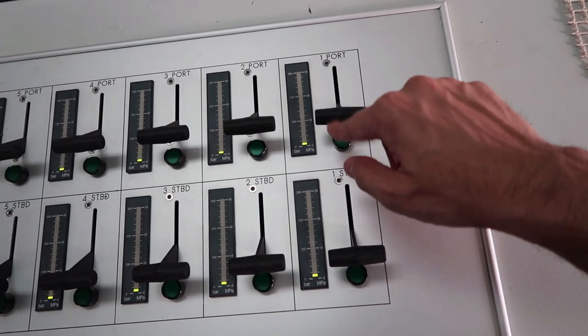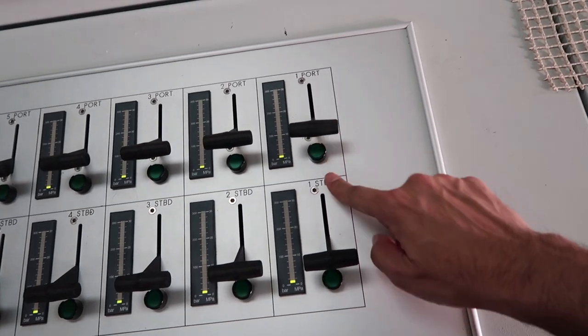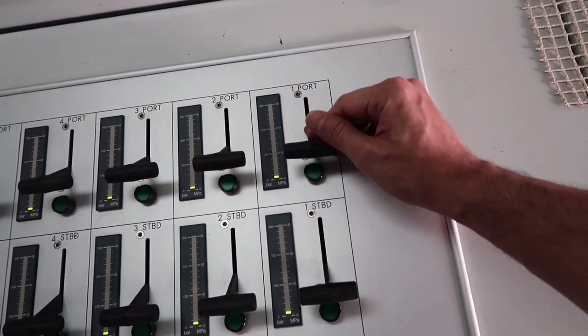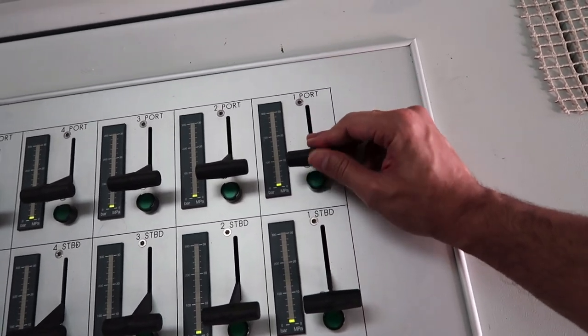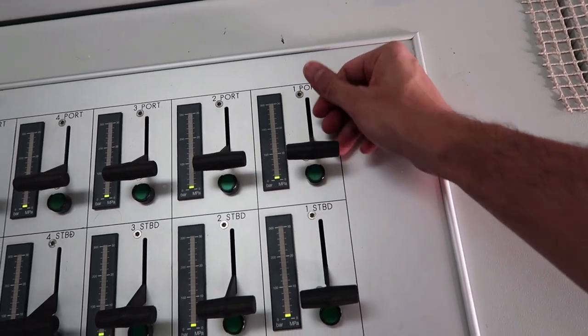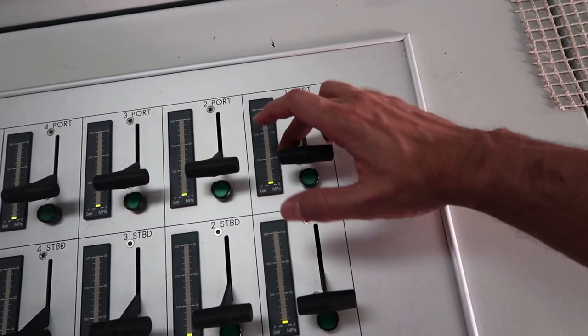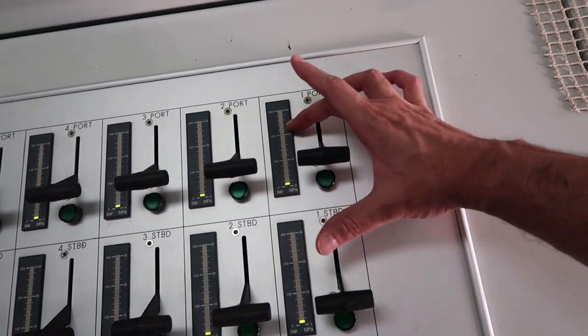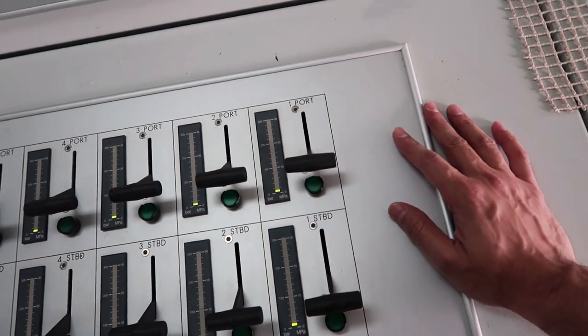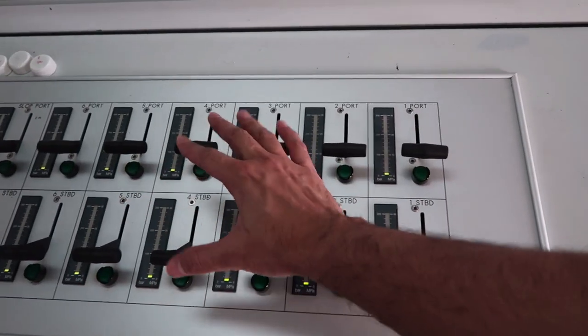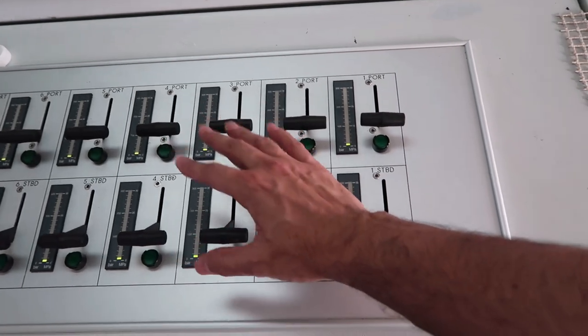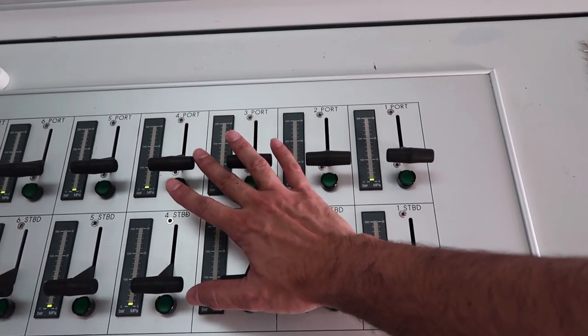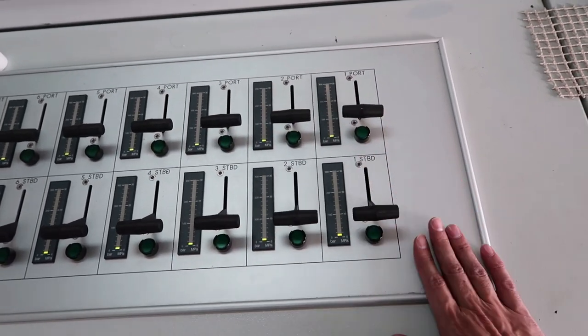So all duty officer need to do is press this button. It will switch on the power for that particular pump. And whatever RPM or whatever pressure you want, you have to increase this lever accordingly. 100-120 will be about 50 percent, 240 will be about 100 percent. Each pump can be set at different pressure and different RPM, different capacities depending upon what we need.